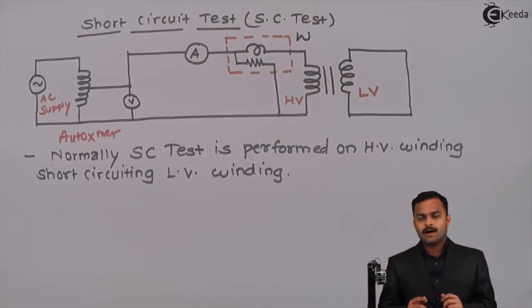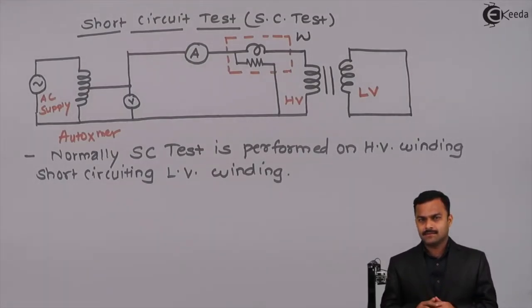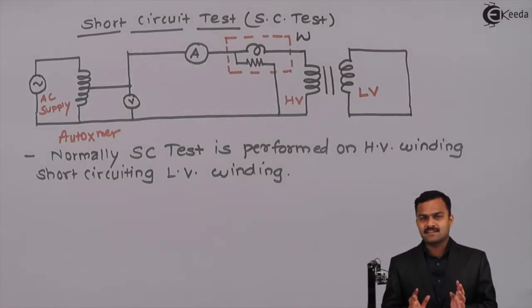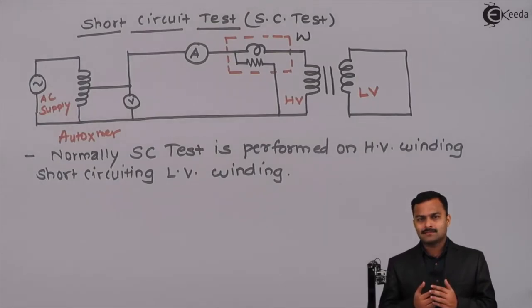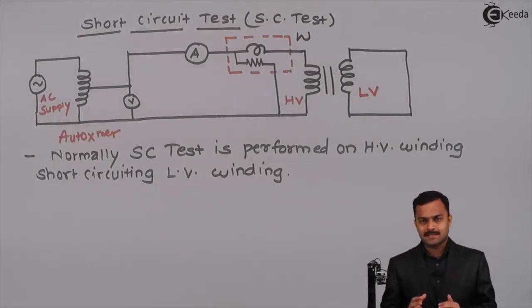Why so? Again, it is because of the restriction of the ammeter. If you perform the test on the low voltage side, a very high current would flow which cannot be measured by the ammeter. That is the only reason — otherwise you can perform both tests on the same winding and get absolutely the same results.